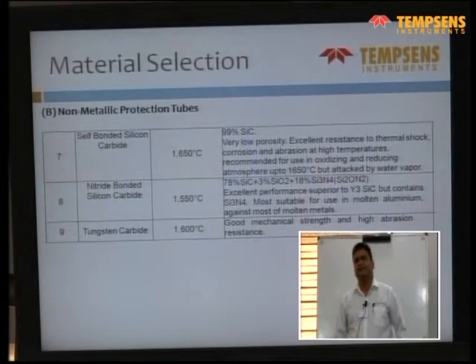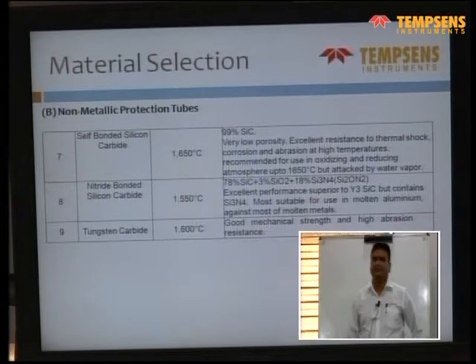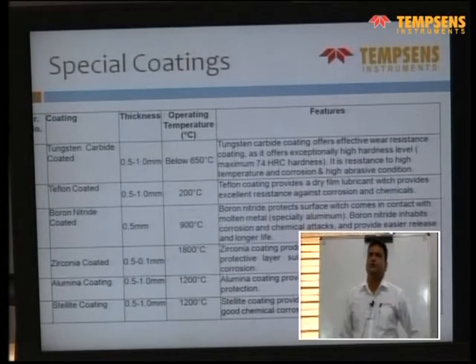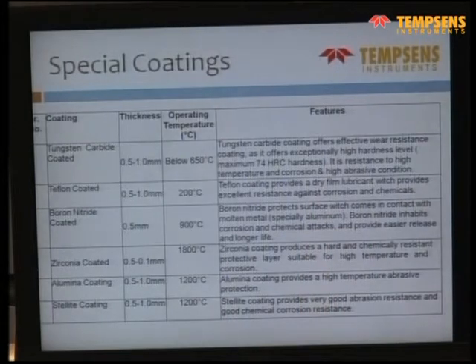The temperature is up to 300 degrees centigrade only in the coal mill application. There are some coatings available. Some of them we have listed here, like tungsten carbide coating. It gives a hard face onto the thermowell, which can offer a hardness up to 74 HRC. Then Teflon coating for chemical applications up to 200 degrees centigrade.